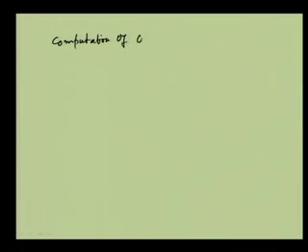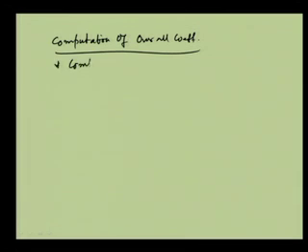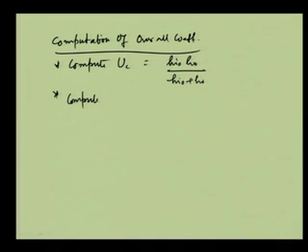So, compute UC, and that is equal to HO times HIO by HIO plus HO, and then compute UD, from 1 by UD is equal to 1 by UC plus RD, already we have discussed, RD is the dirt factor.